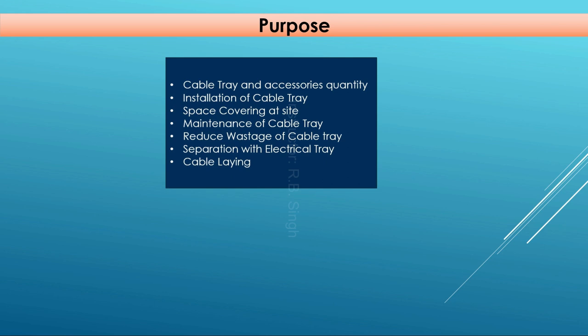Separation with the electrical tray is very important. The separation between electrical cable tray and instrument cable tray must be maintained: for voltage up to 120V, 300 mm separation is required; up to 400 or 440 volts, 600 mm spacing is required; and for HT cables, at least one meter gap between the two trays is important. These separations can be shown on the cable tray layout so that they are maintained at site. Also, if you have the cable tray layout, cable laying will be much easier.